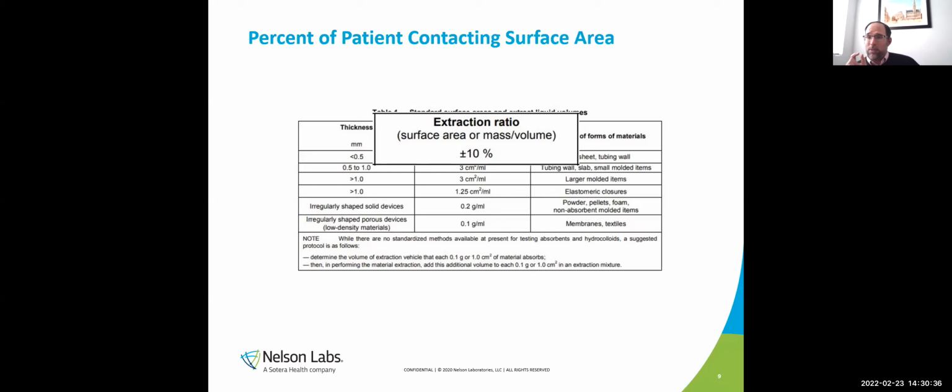If you're changing less than 10% of that, then the risk to the patient is a lot less than if you're changing more. So if you start to change 10 to 50%, that starts to become a little bit more risky. We have to do a little bit more evaluation or testing, need more information. If it's over 50%, then you're basically doing a new device, right? So then you are kind of more stuck doing your normal biocompatibility evaluations.